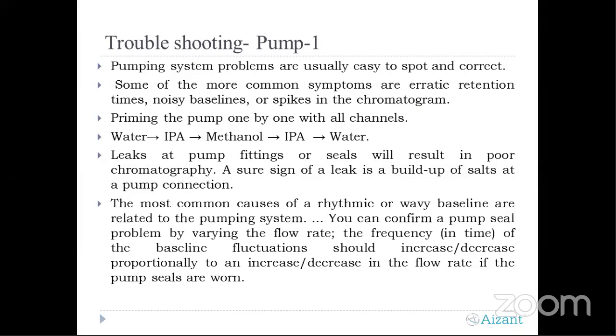We have to always prime the pumps, and the sequence of priming all pumps should be: first we should prime the system with lukewarm water, followed by isopropyl alcohol and then methanol. And then we have to go back in the same way; after methanol, don't jump directly to water, go again to IPA, which is miscible in organic as well as aqueous systems.